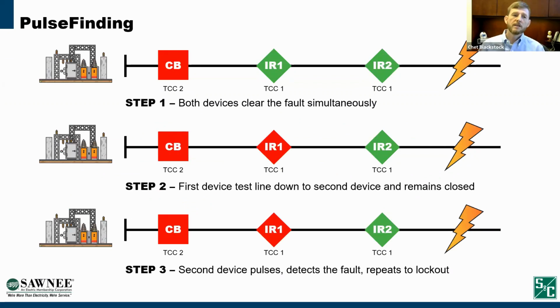So this is how we deployed pulse finding initially. This is exactly how Mike described. Two interrupters would be in series with the same TCCs. Both would clear the fault simultaneously. The next step, TCC1 or interrupter 1 would test and hold down to the downline interrupter. And that downstream interrupter would then test, detect the fault all the way to lockout, and then remain locked out. So you would get one blink on the interrupter upline, but after that, the interrupter upline wouldn't operate unless you had a recurring fault. Next slide.